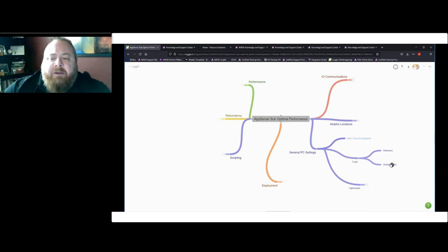And then from there, I'll probably start in the Wonderware log files after I go through the PC log files. Those can be accessed in a number of different ways. It's through the System Management Console, the SMC, the System Platform Management Console, depending on the vintage of software that you're using. But it's the Wonderware Logger, as we lovingly call it. You can expand it out and go into the default group there. If you have AppServer where you have Galaxy deployed, it will also add those remote nodes. A lot of people don't know that, but from one place you can sit and diagnose and see errors, warnings, and info.